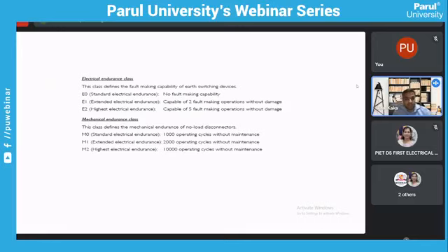these are some of the endurance classes, electrical as well as mechanical, for which our breakers are being tested. E0 is normally the standard endurance class with no fault making capacity, which defines the fault capacity of earthing devices. E1 is an extended electrical endurance capable of 2 fault making operations without damage. E2 is slightly higher with 5 fault making operations without damage. And the mechanical endurance classes are M0, M1, and M2.